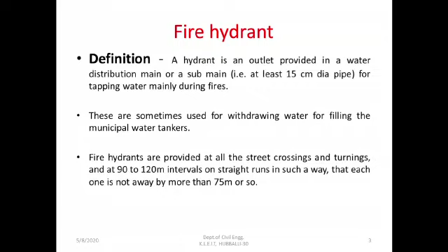It's not only for extinguishing fire, but it is also used sometimes for withdrawing water for the filling of municipal water tankers. Where it is provided, it is provided at all the street crossings, at the turnings, and at 90 to 120 meter intervals on straight runs. If there are no turns and bends in the street, if it is a straight road, then at an interval of 90 to 120 meter, these fire hydrants are to be provided. And each one should not be away by more than 75 meter or so.